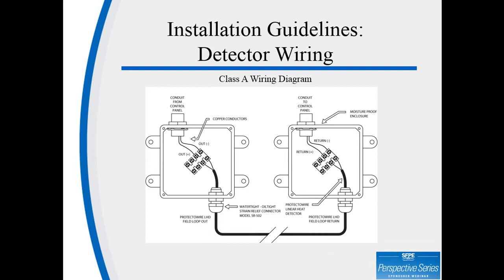Coming out of the other side of the PWSC, you'll notice that it changes to the Protectowire, then goes through the SR502 strain relief connector. That strain relief connector prevents it from being pinched and also seals the box from water penetration. The loop carries on until you get to the junction box at the end of the loop, where you transfer back to interposing cable using the same PWSC and the conduit going back to the control panel in a Class A configuration.